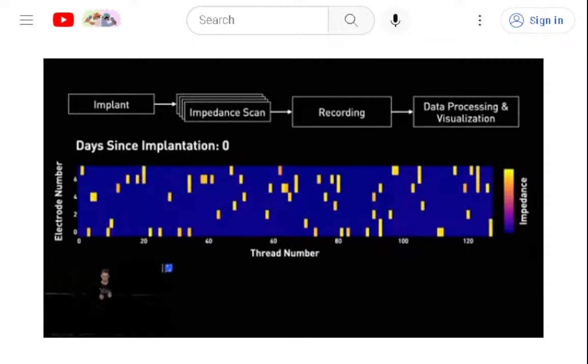In our original implementation of doing these impedance scans, it took 4 hours to get through all 1,000 channels. But by parallelizing the tests, downsampling, filtering, and then reducing the amount of information we have to stream off the device by moving a lot of the calculation to the firmware side, we're now able to scan all 1,000 channels in just 20 seconds. This means that we can run impedance on every implant every day.